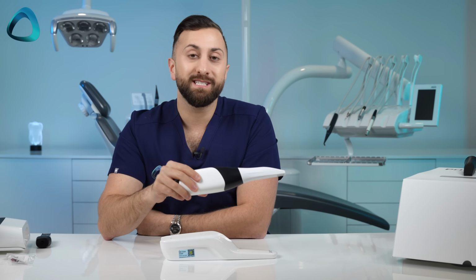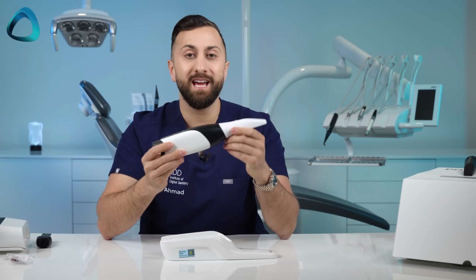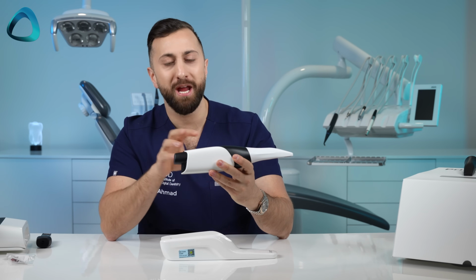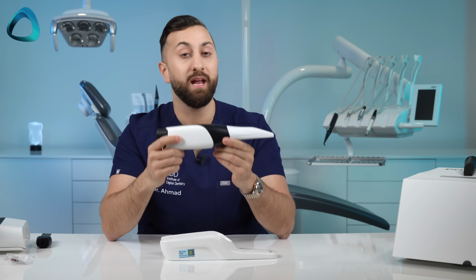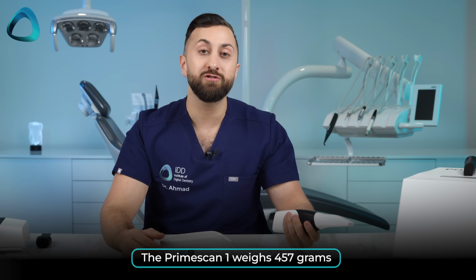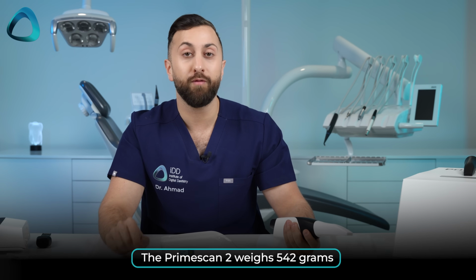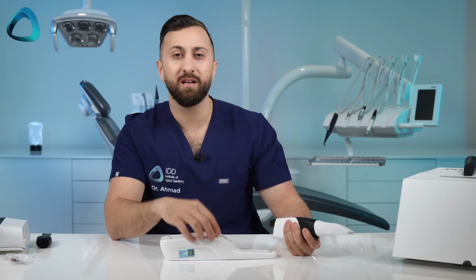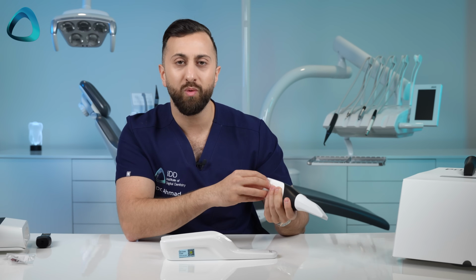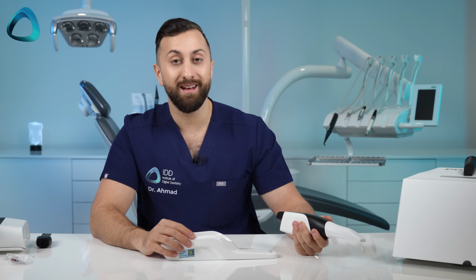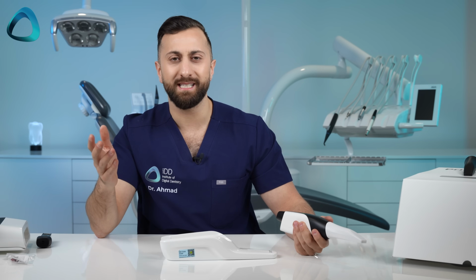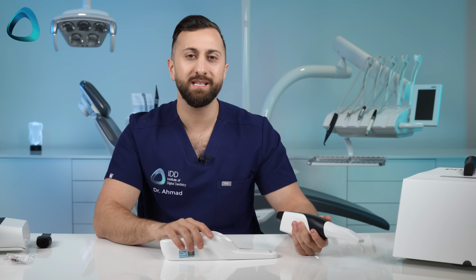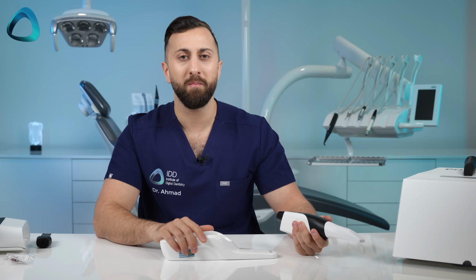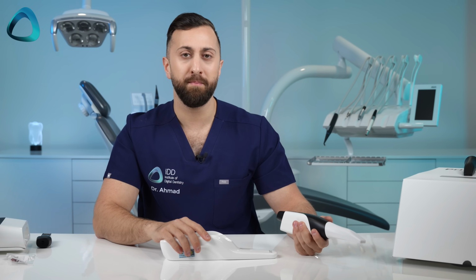The other thing about the Primescan 2 is the weight and size. The Primescan 2 is a bigger unit, and although it shares the same shape as the Primescan 1, it is larger overall and weighs more. The Primescan 1 weighs 457 grams, the Primescan 2 is quite a lot heavier, almost 100 grams more, at 542 grams. Obviously, with wireless scanning technology, scanners become heavier because of all the extra hardware, the batteries, etc. And this does mean that the Primescan 2 is easily the heaviest scanner on the market right now, at least with the new releases. And it's an interesting move because most other companies are trimming the weight off their scanners, as we're seeing from Medit, Shining, even Trios 5 compared to Trios 4.